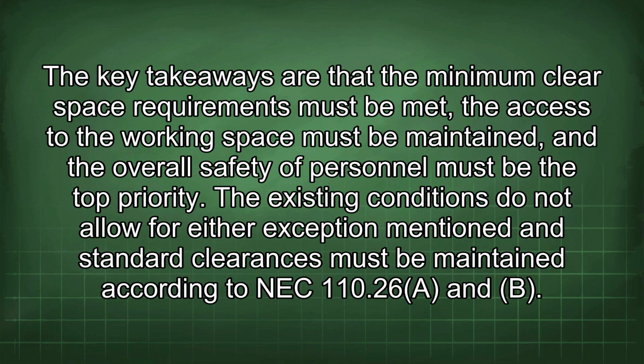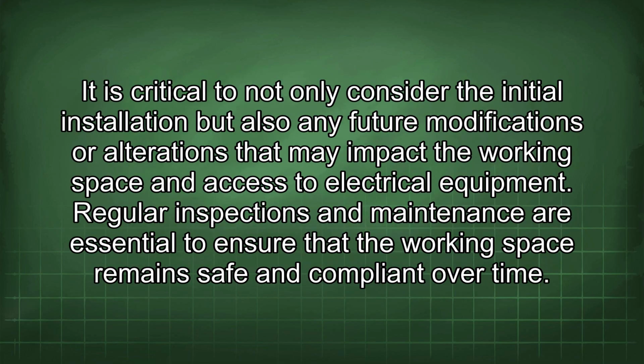The key takeaways are that the minimum clear space requirements must be met, the access to the working space must be maintained, and the overall safety of personnel must be the top priority. The existing conditions do not allow for either exception mentioned, and standard clearances must be maintained according to NEC 110.26(A) and (B). It is critical to not only consider the initial installation but also any future modifications or alterations that may impact the working space and access to electrical equipment. Regular inspections and maintenance are essential to ensure that the working space remains safe and compliant over time.